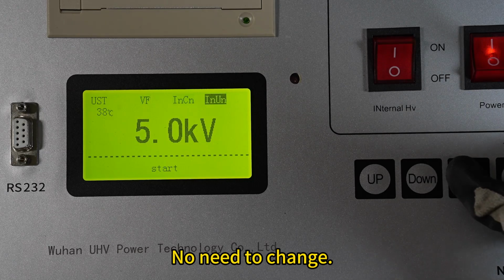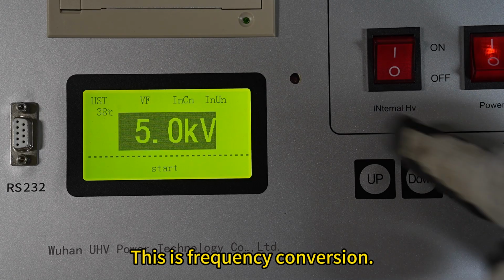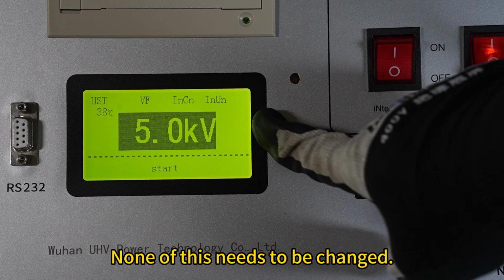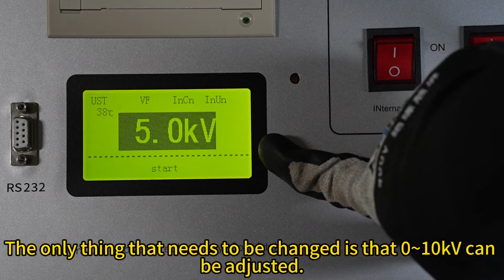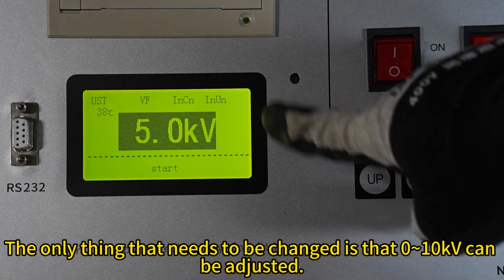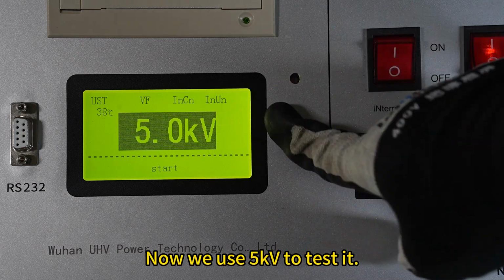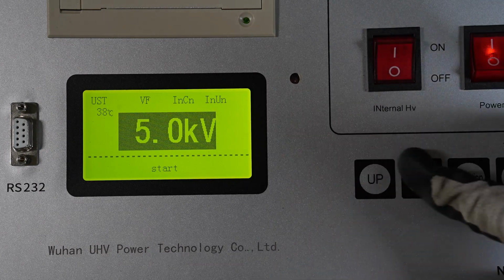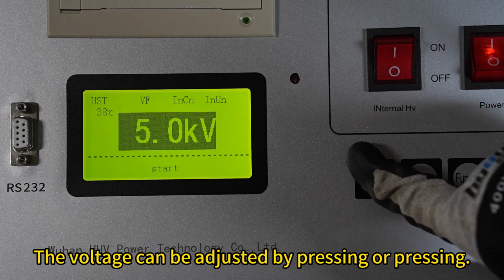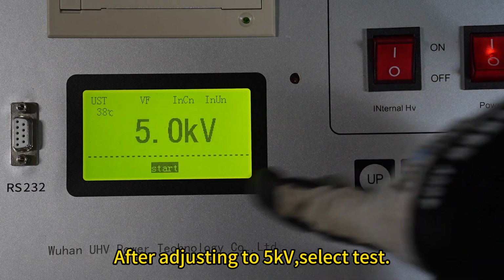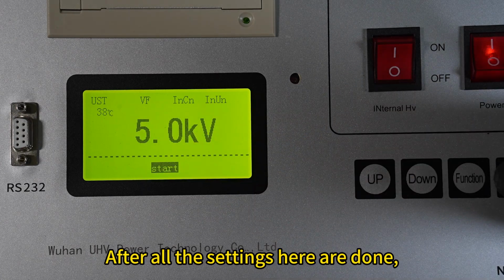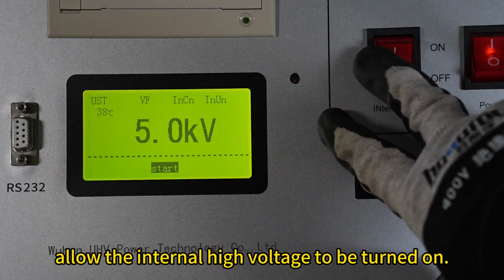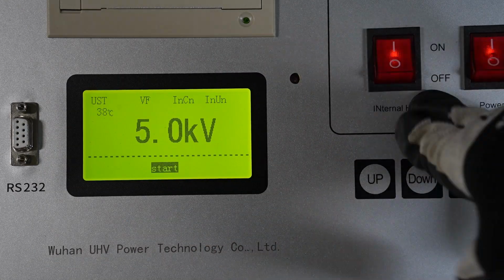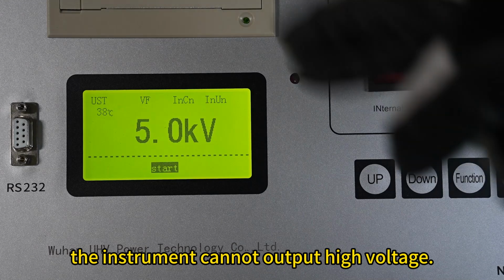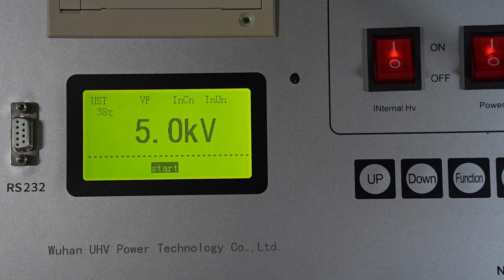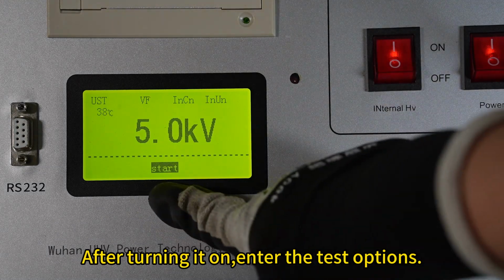No need to change. This is frequency conversion. None of this needs to be changed. The only thing that needs to be changed is that 0-10 kV can be adjusted. Now we use 5 kV to test it. The voltage can be adjusted by pressing up or down. After adjusting to 5 kV, select Test. After all the settings here are done, allow the internal high voltage to be turned on. If this switch is not turned on, the instrument cannot output high voltage. After turning it on, enter the test options.